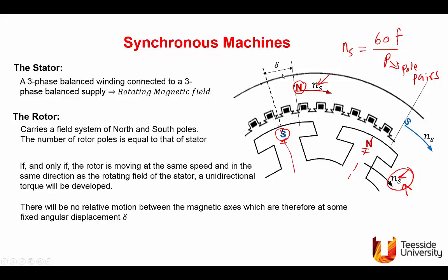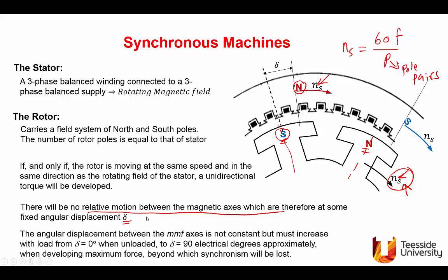When the machine is synchronized, there is no relative motion between the magnetic axes and angle delta is zero if there is no load and no losses. As the load on the machine is increased, angle delta will increase. If it keeps increasing and reaches 90 electrical degrees, the coupling between the south pole and the north pole of the rotor will be lost, and we say synchronism will be lost.